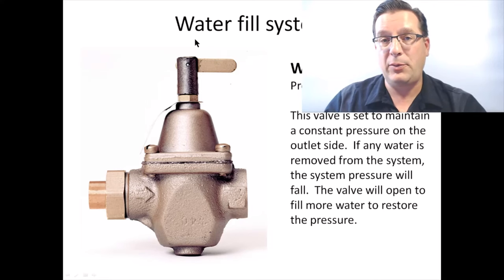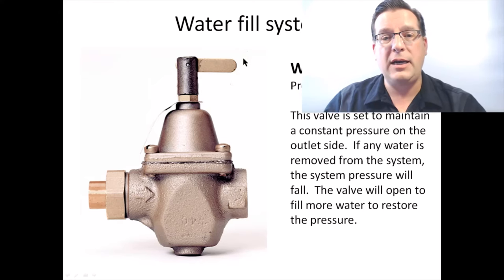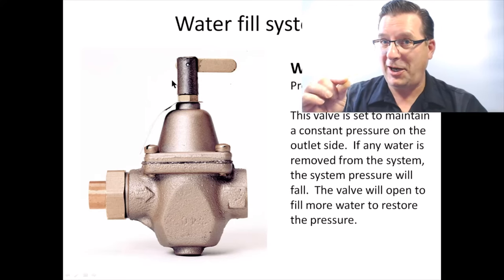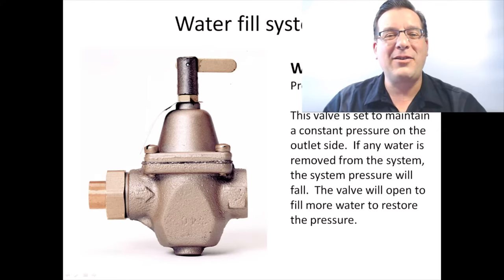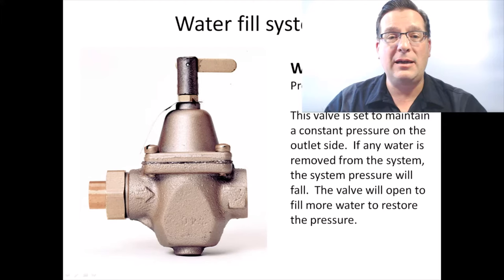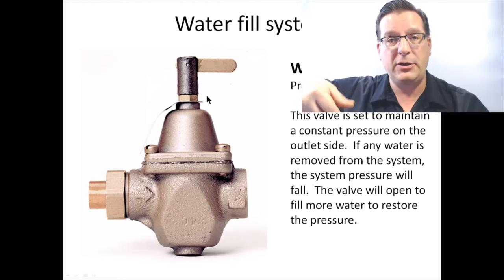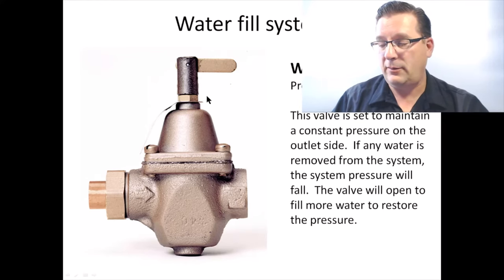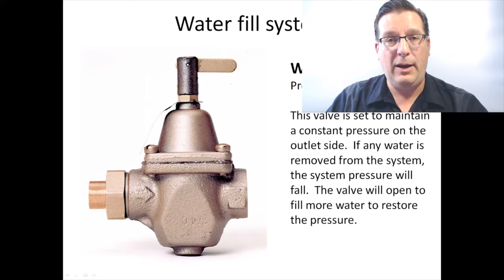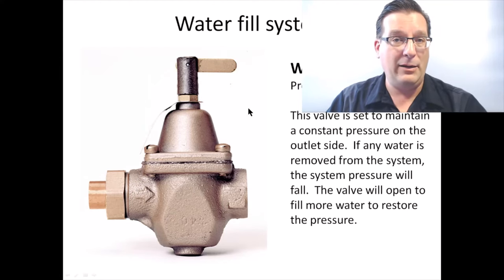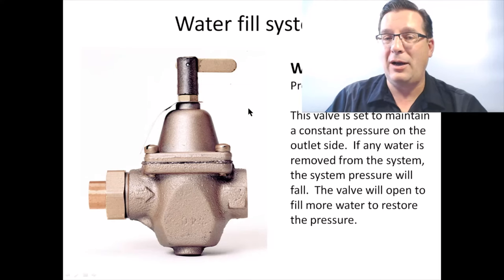To adjust this particular pressure reducing valve: first, unscrew the little top that has the fast fill handle. As soon as you take that off, there's going to be a little metal rod sticking up — pick that up and don't lose it. Next, this nut here is just a lock nut to stop the adjustment from changing — simply loosen it up. Now the threaded collar is your pressure adjustment. There's a little screwdriver slot in the top: screw it in to increase pressure, screw it out to decrease pressure. Once finished, tighten the lock nut back down, put the metal rod back in, and tighten the top back on. Done — not too tough.